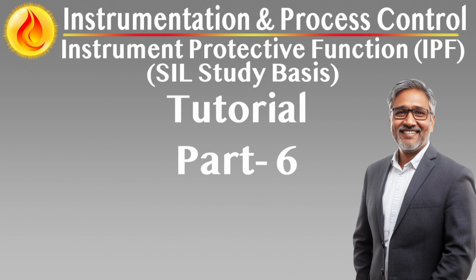Principles for safe communication integration. One-way data flow from IPF to other systems. IPFs may transmit status, alarm, and diagnostic data to external systems, but external systems must not have the ability to modify IPF logic, parameters, or bypasses. Read-only integration preserves visibility without risk of interference.